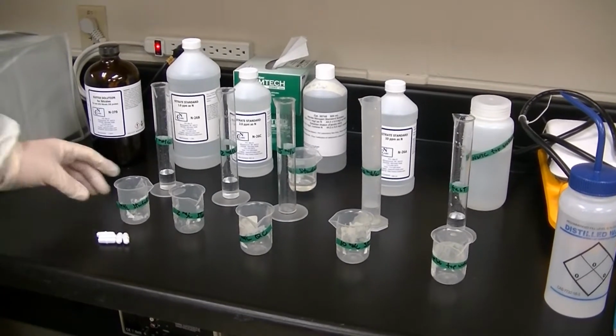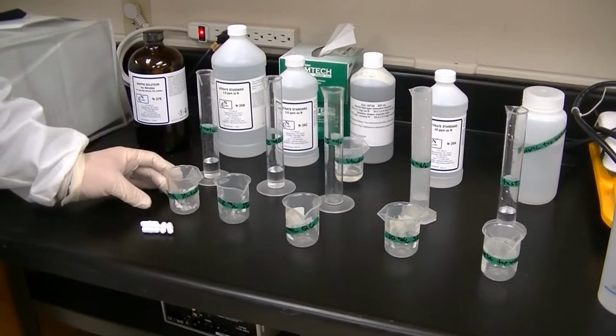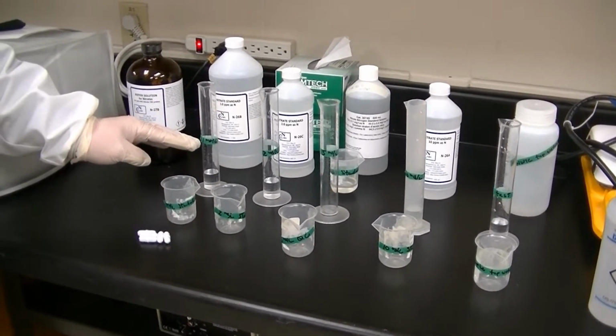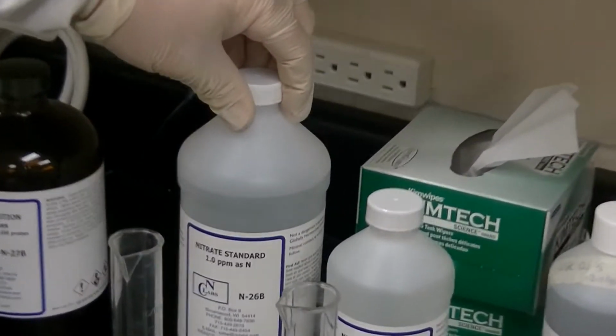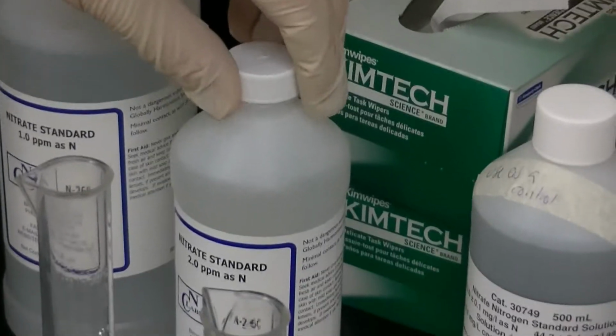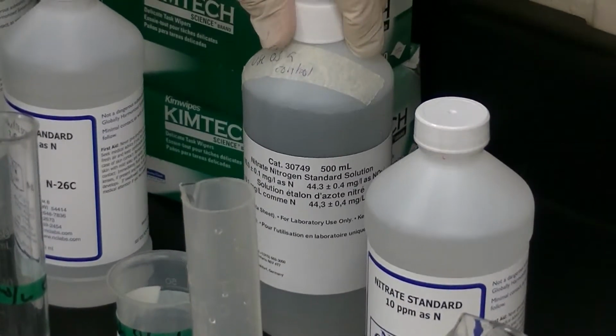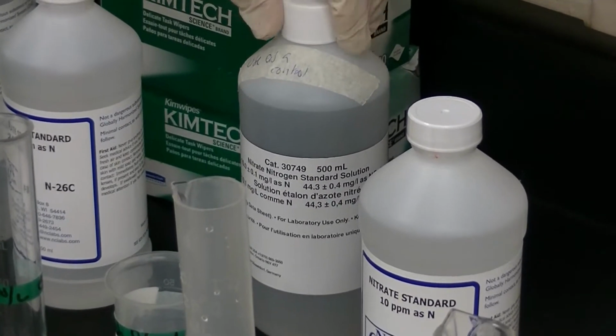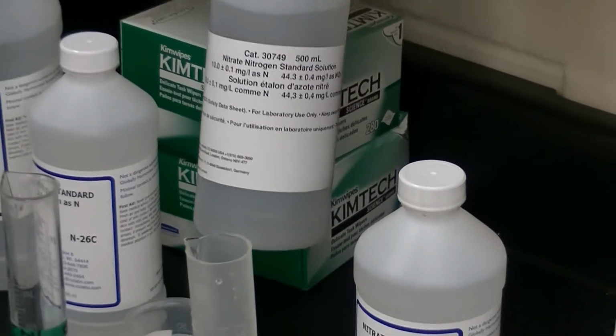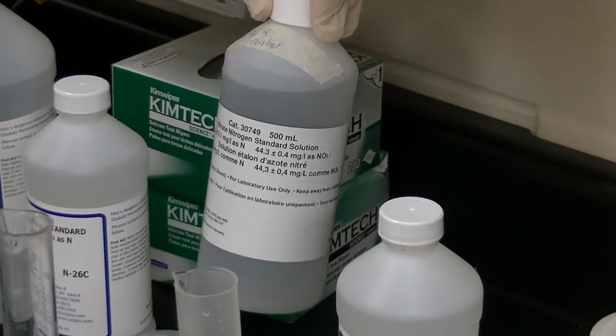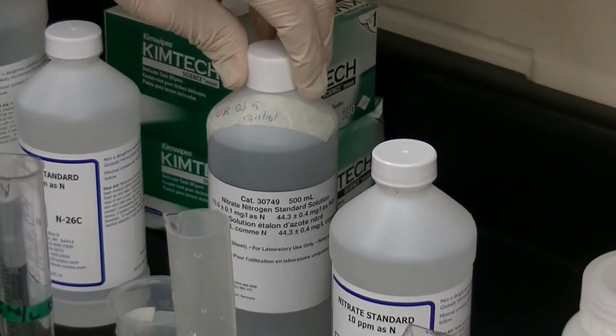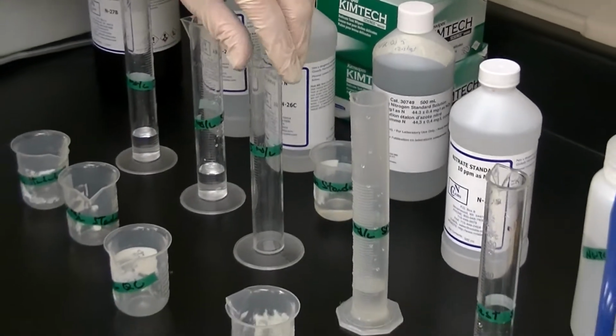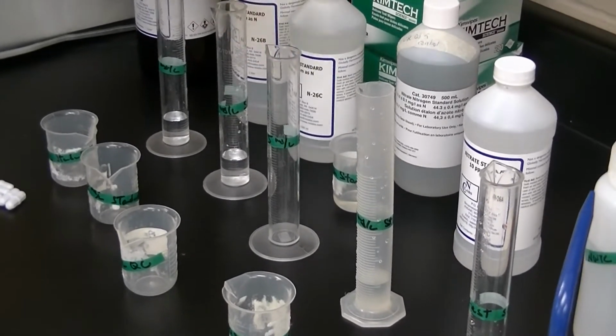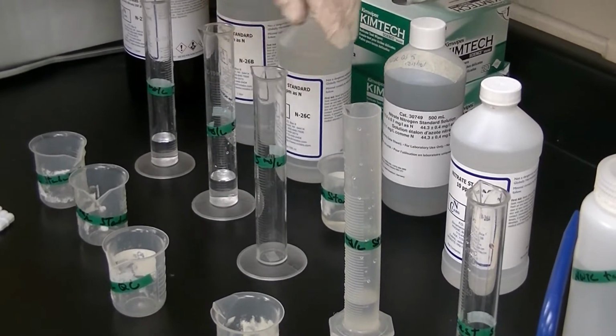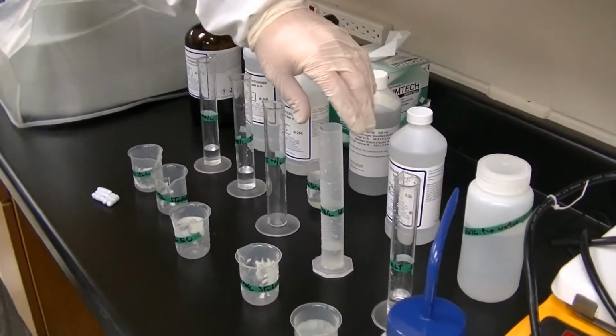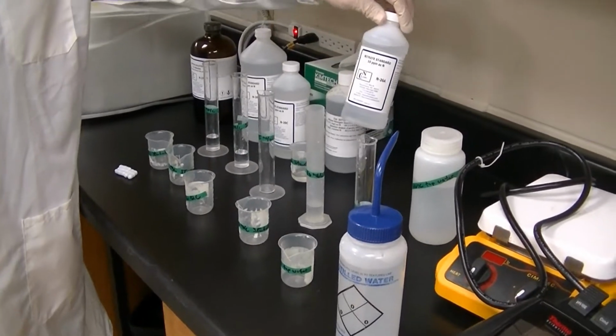So what we have set up here is some all plastic ware. We've got a 1 milligram per liter standard from North Central Labs. We have a 2 milligram per liter standard, also from North Central Labs. In the middle here, we're going to prepare a lab fortified blank for QA/QC. For that, we want to use a nitrate standard from a different source. Here we have the standard from the HACH company, 10 milligrams per liter. For that, I'm going to make up a 5 milligram per liter lab fortified blank, and we'll use that to test how well our calibration went on the nitrate probe. I'll show that dilution here. Our last calibration standard is a 10 milligram per liter, also from North Central Labs.